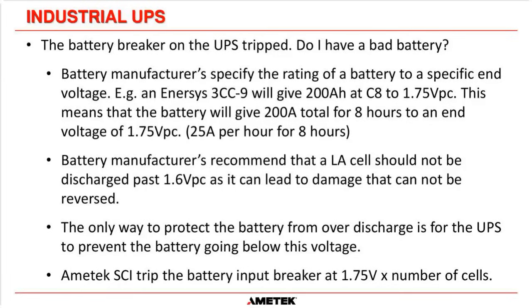And then at the end of those 8 hours, our expectation is the battery will be around about 1.7 volts per cell. So let's get that out of the way. The next thing is the battery manufacturers recommend that a lead acid cell should not be discharged past 1.6 volts because that can lead to damage that cannot be reversed. Okay, so there's a buffer there. We say 1.75 volts is the best voltage to go down to, but there is a little bit of leeway. They could go down to 1.6 volts and they'll still be okay. Go below 1.6 volts and all bets are off.